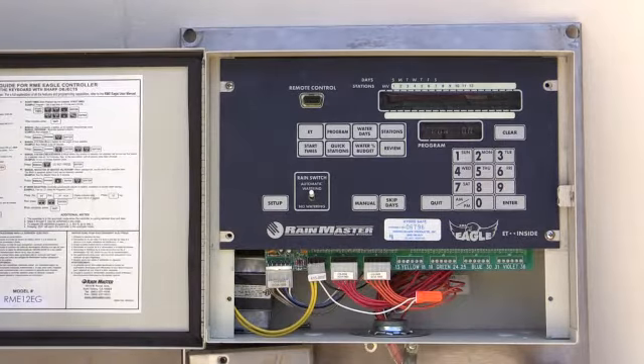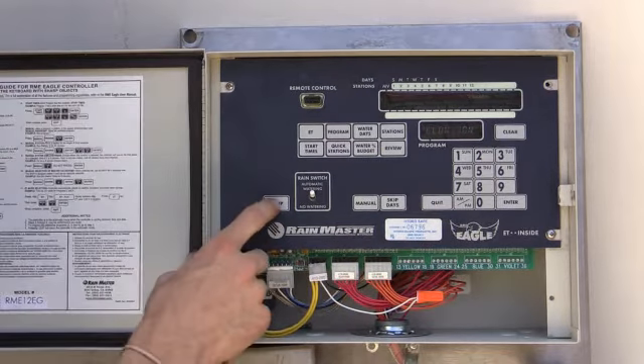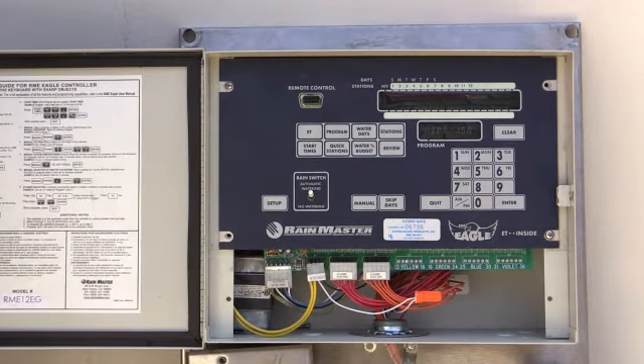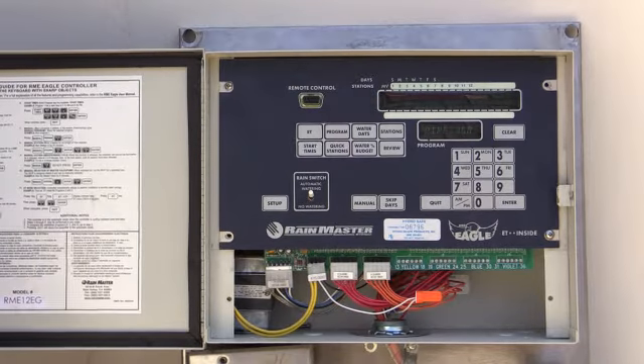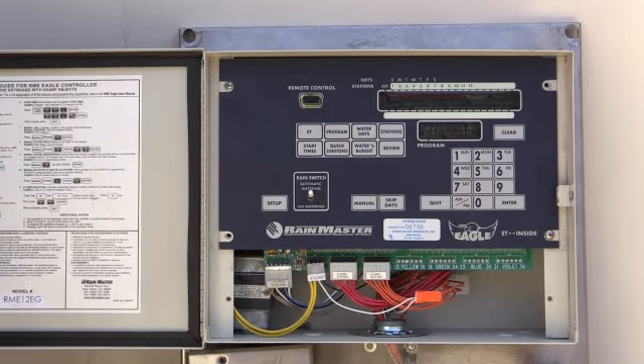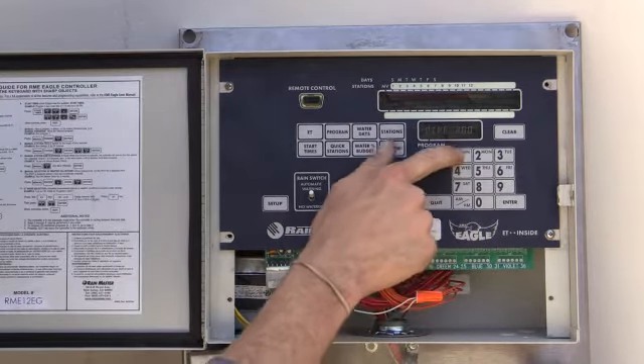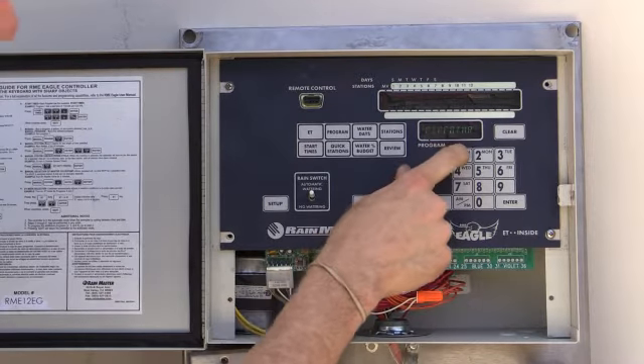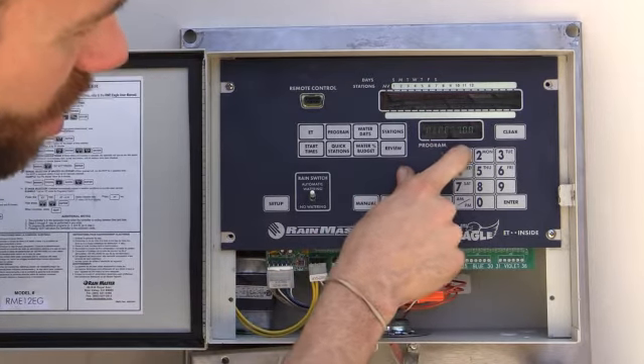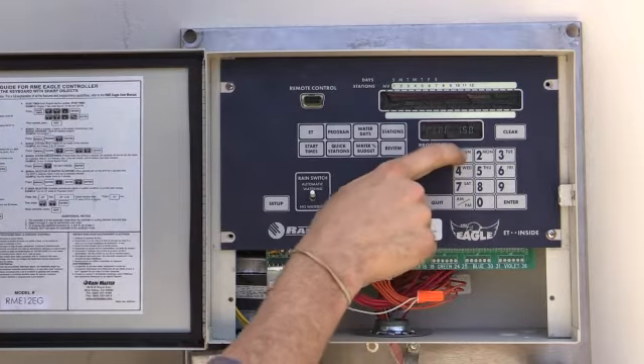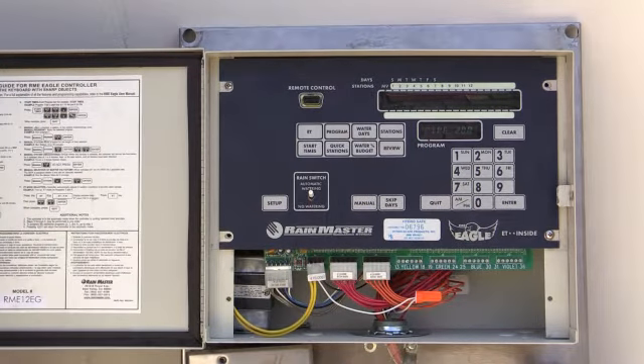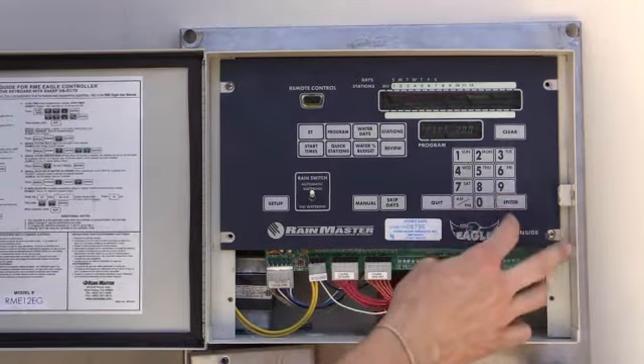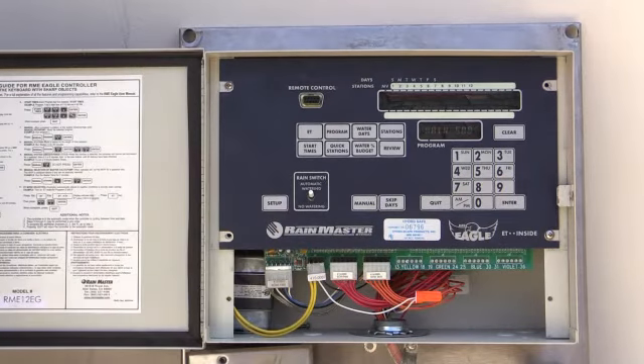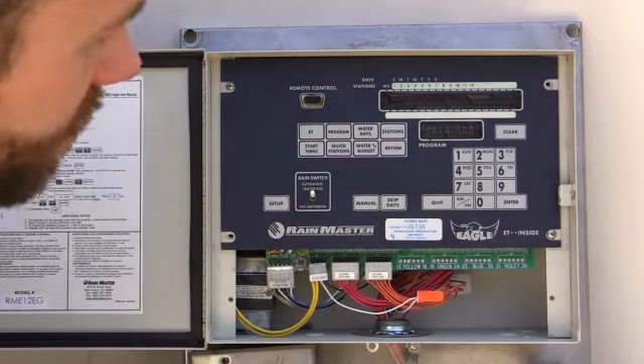Now it's going to start asking me some questions about my flow sensor. What size is the pipe? 1.5 is 1.5 inches. You can hit 1 to toggle - we've got 2 inch, 3 inch, 4 inch, 1 inch, 1.5 inches. I'm going to go ahead and say 2 inch, hit enter to save, and hit setup to advance.